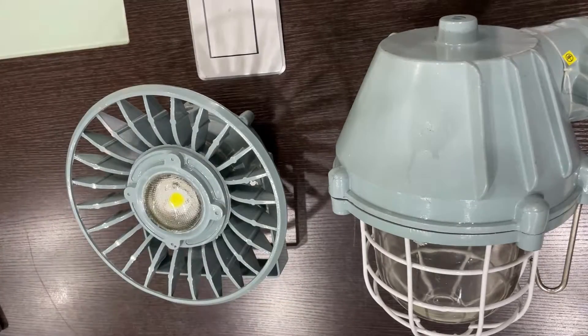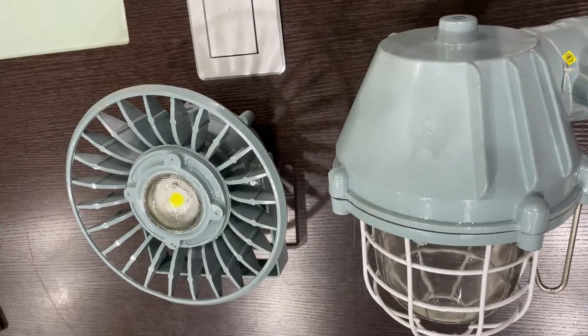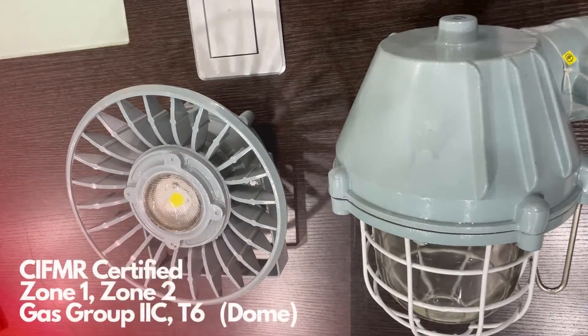It comes with multiple wattage options. You can choose between 45, 65, and 75 watts depending on your individual lighting needs. As we all know, safety is extremely paramount in hazardous areas. Rest assured, the dome light fitting is CIFMR certified specifically for zone 1 and zone 2, and Gas Group IIC, T6.